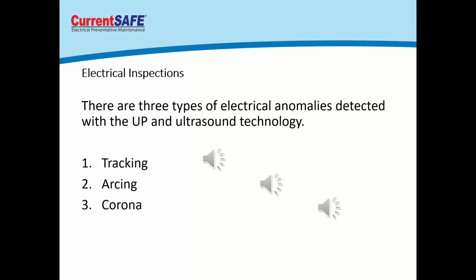So what tracking is, is electricity building up and eating away at the insulative properties of the distribution system and making its way to ground. So tracking is exactly that. It's tracking a path from an energized component to a grounded component or a grounded surface. And so that tracking is the eating away and deterioration of the insulation between energized and ground. Now, once it reaches a path, we can get arcing. So the tracking is the eating away of that.